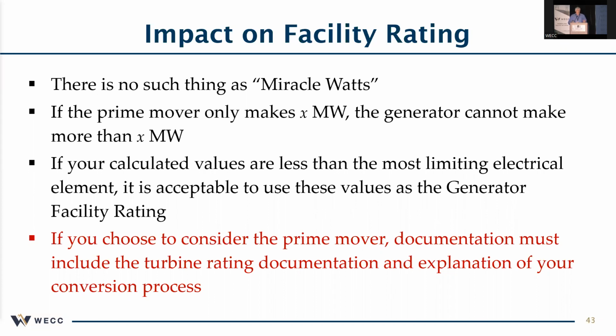You can't create something from nothing. If the actual prime mover horsepower can only put out X number of megawatts, there is no way other than momentarily during faults that you're going to get more power than that out of the generator side. If it only makes X megawatts, the generator can't make any more. So if you do choose to consider prime mover, that's fine. Just include the documentation as to how you made that rating determination so that the auditors can duplicate it.